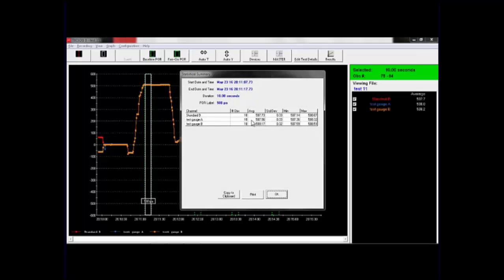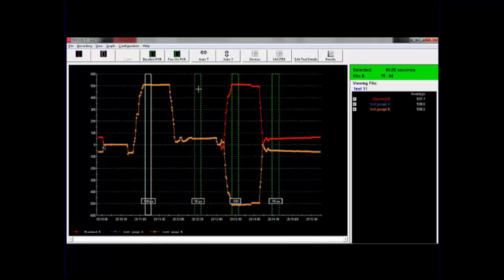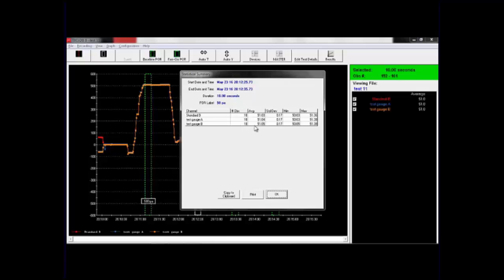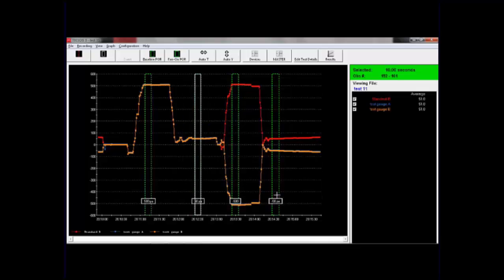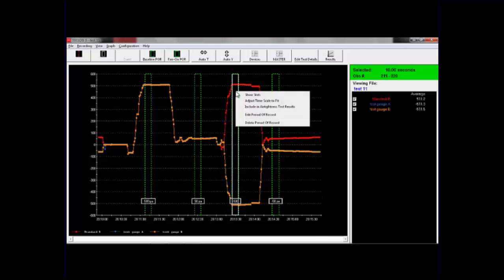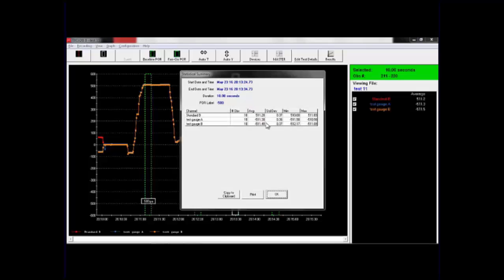Now we can look at our information and see if we're at 500 pascals, we want to be within 5 pascals, and we're within less than 1 pascal. So we're easily within 5 pascals difference from the standard gauge to those other 2 channels. So that one's good. We'll look at, so I'm going to click inside that green box at +50, show stats. Now we're at 50, we want to be within 0.5, and we're within 0.01, 0.02, so we're really good on that one also. And then -500, show stats. We need to be within 5, and we're within less than 1.